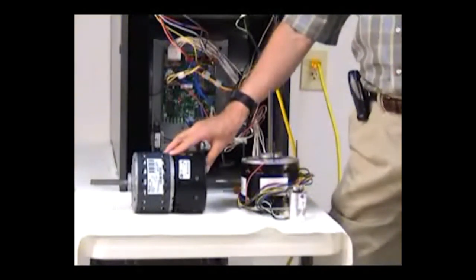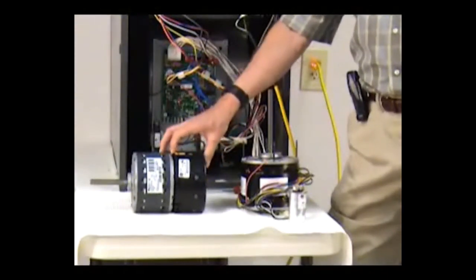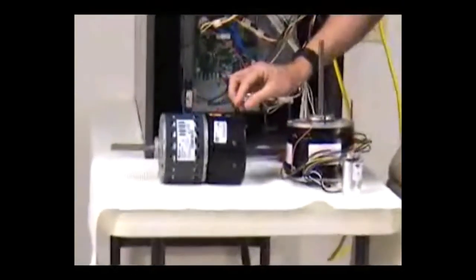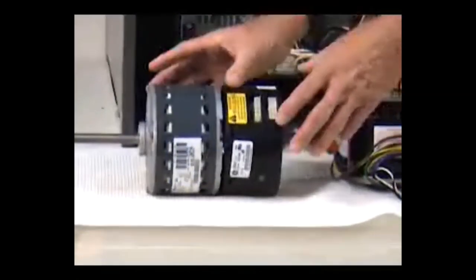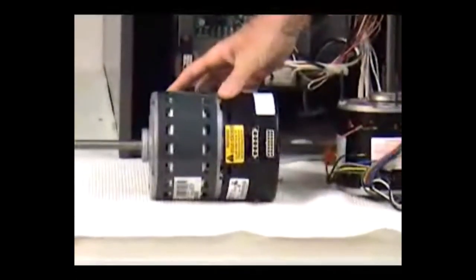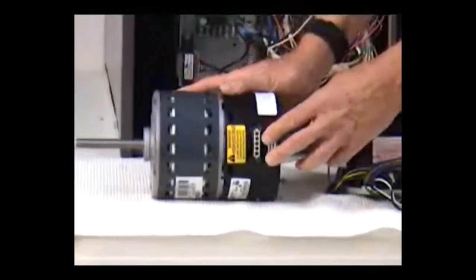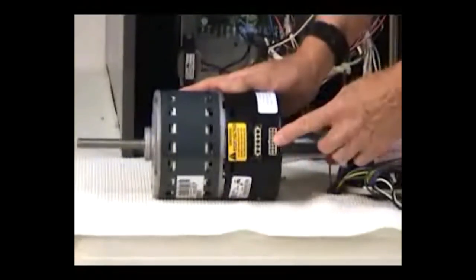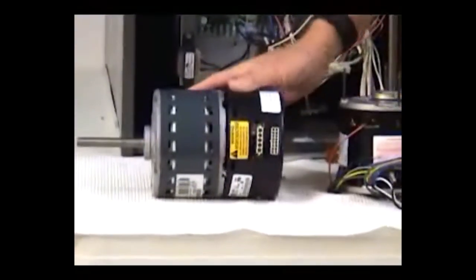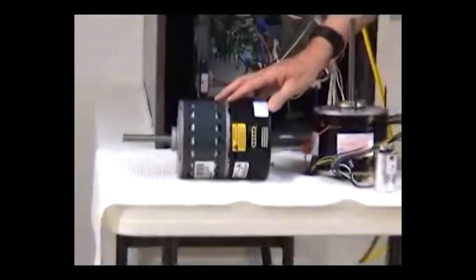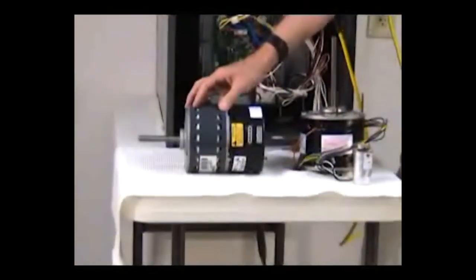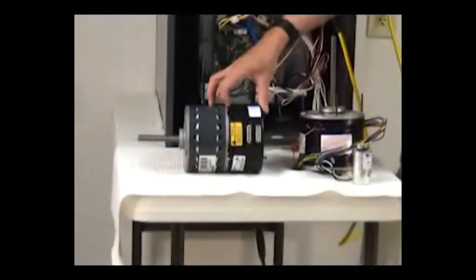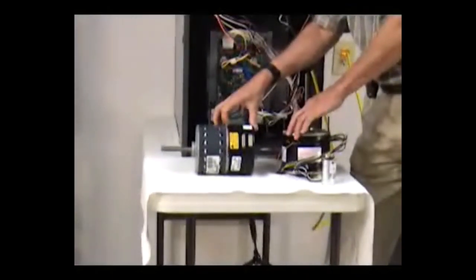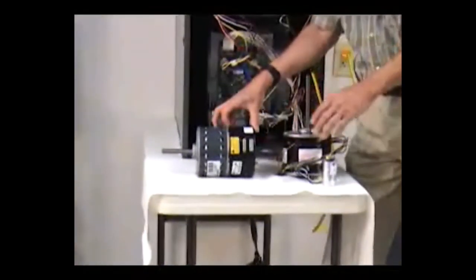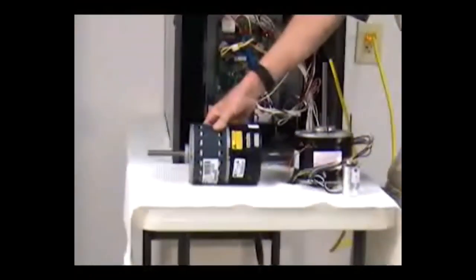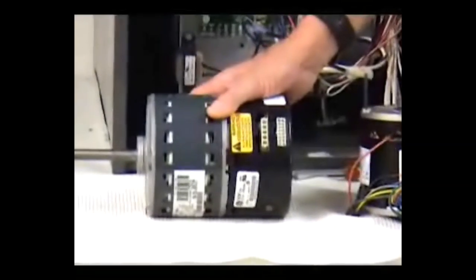The module serves two major functions for the ECM motor. One is that it is going to deliver not only low voltage, but also high voltage to the motor, whereas we're delivering only high voltage to split capacitor motors. You have terminal blocks here that will give you high voltage and low voltage. Low voltage on this side, high voltage on this side here. The module can be removed from the actual base motor itself. This module is going to take voltage that we send to it, whether it be 115 volts or 230 volts. It will take this voltage and convert it to a DC current to the motor itself. The motor is basically a DC motor.